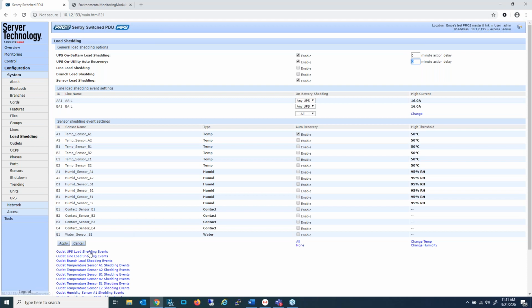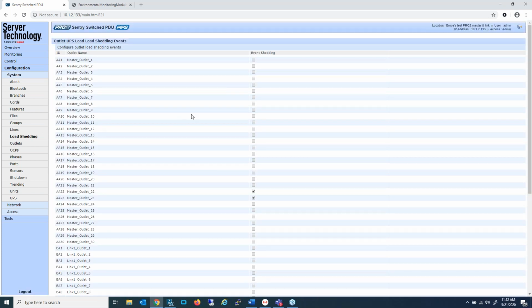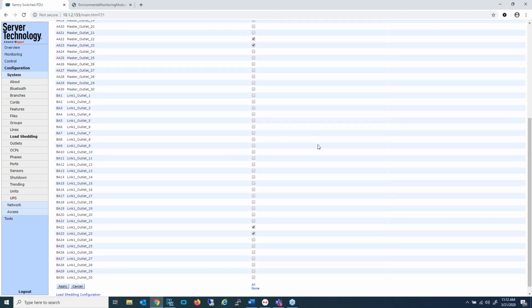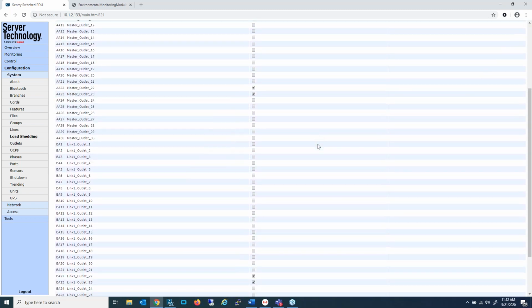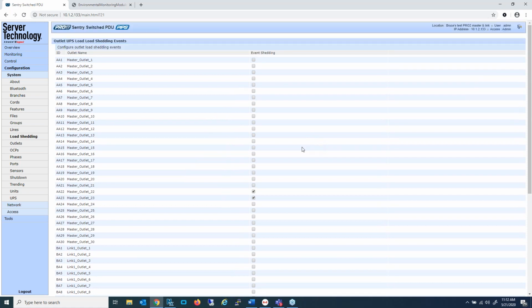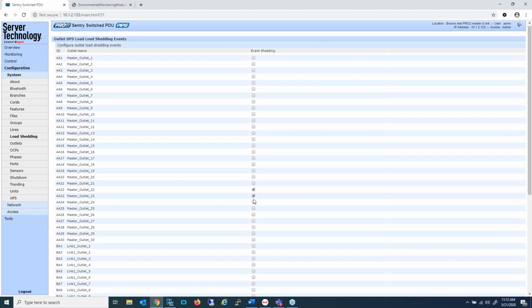Okay. So the final step for an on battery load shedding event is to go down to the link here and select the outlets that you wish to be switched off when the UPS loses utility power. The idea again is non-critical equipment. I have selected 2 outlets on my master PDU. This is a 30 outlet PDU, so I've got A1 through A30. I've selected outlets 22 and 23 to switch off.